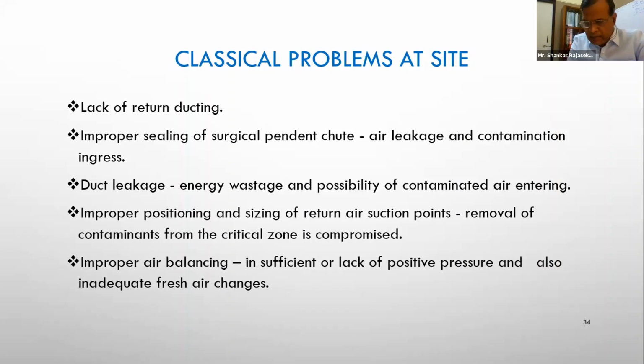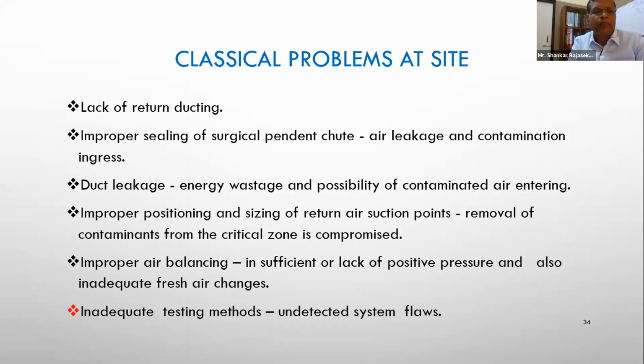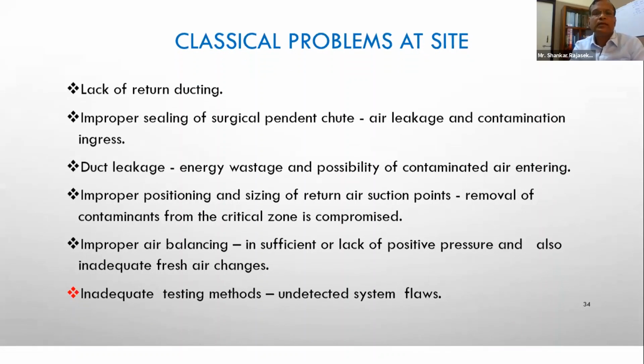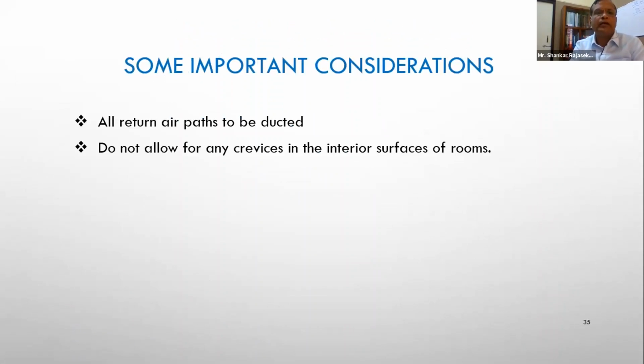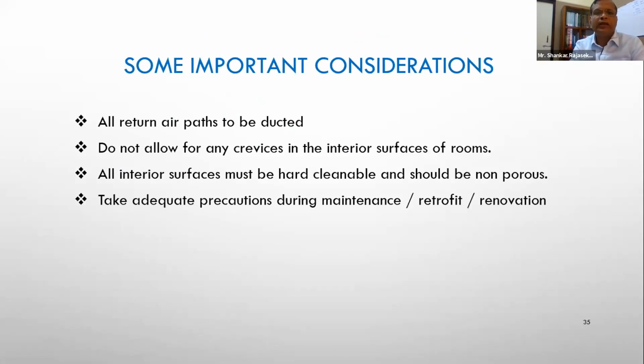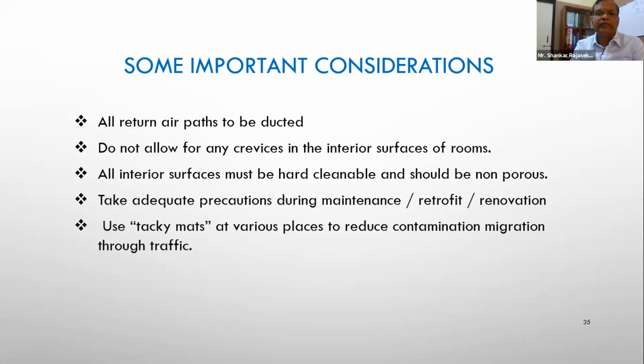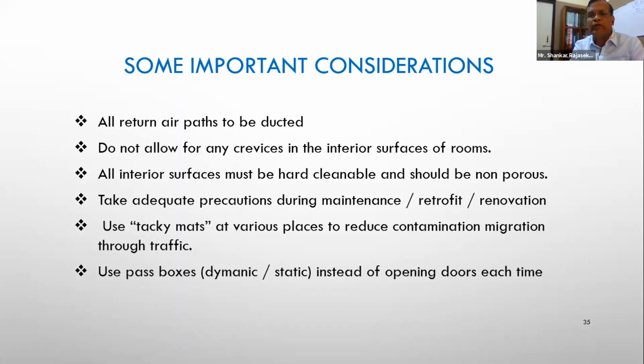Many times I see that the pressure is not getting built up because of improper air balancing. And mostly inadequate testing methods, so we don't detect the flaws. So what are the points to be considered? All return points to be ducted. Do not allow for crevices. All interior surfaces must be hard and cleanable. Adequate precautions during maintenance, retrofit and renovation, because maintenance, retrofit and renovation is a time which actually spreads contamination around, and there are clear-cut documents for this.